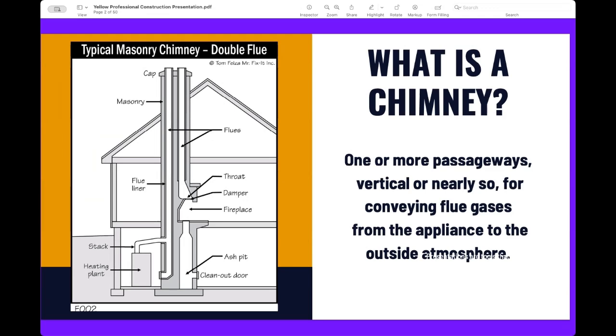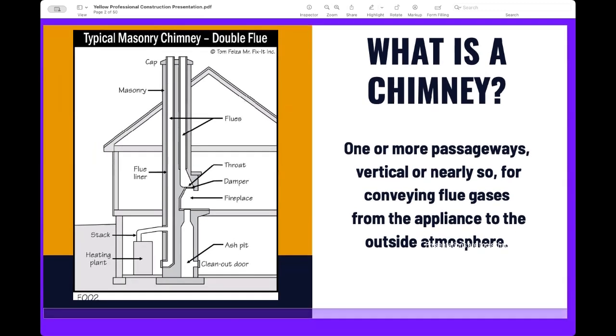So yes, Rachel, this picture exactly. The boiler should be all by itself going all the way up, but it would be like below the words flue liner on the left side. They banged it over into the throat of the chimney, and the chemical composition of the oil mixing with the fireplace and the water coming down the chimney, because there was no rain cap, was eating the flue liner. So this house had some work to do to help the house live another 100 years.